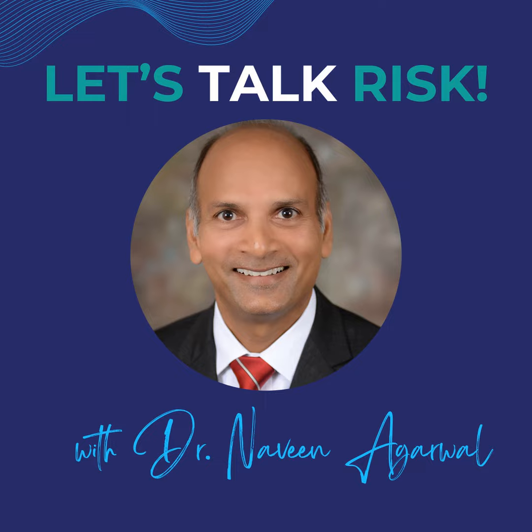And also, I think this makes a lot of sense to me because what I have seen in my practice, many times we focus only on the severity level. We say if severity is high, we want 99% reliability; if it's medium or low, less. So we are not even talking about risk, we are talking about just severity, right? So that's one point. The second point is that many times you want high reliability even when the severity of the potential harm is low because it causes a lot of nuisance or inconvenience to our customers.